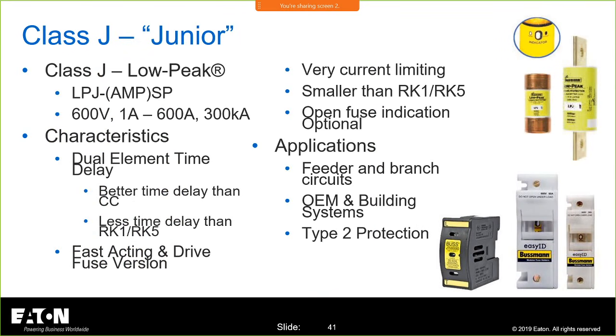J is for junior. Class J is junior. They're not tiny. They're not large. They are junior. And they go up to 300,000 amps, up to 600 amps, 600 volts. You're not going to get these in 230 or 240 or 300 volts. These are 600 volts, dual element time delay, and fast acting. Feeders and branch circuits is where you'll find these.